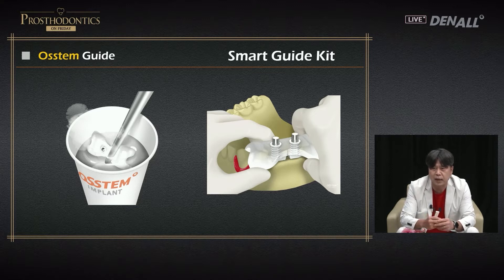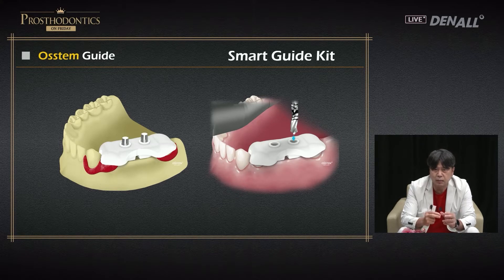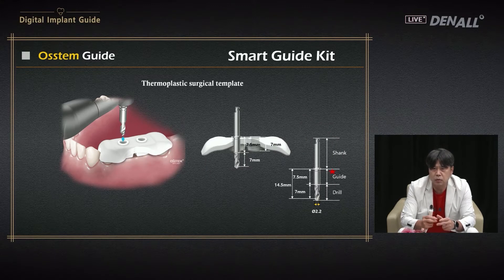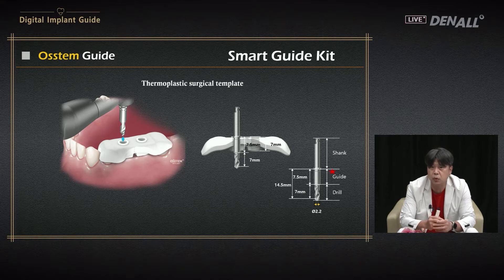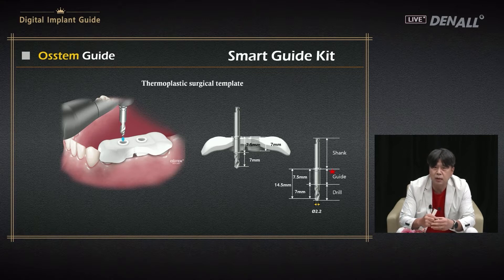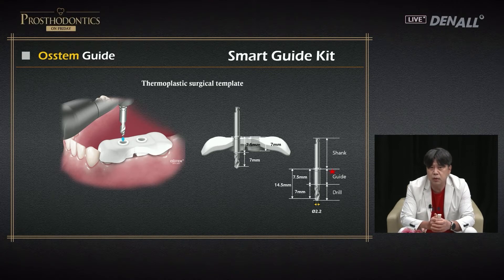The smart guide kit uses thermoplastic material. It is dipped into hot water at 60 degrees Celsius for a minute, then becomes soft and moldable. On a model, a guide is made; after a minute in room temperature it hardens. After sterilization, it can be used for drilling. If you use the smart guide, the distance between implants and the tooth can be controlled, axial inclination can be controlled, and the depth is limited — for example, to seven millimeters.